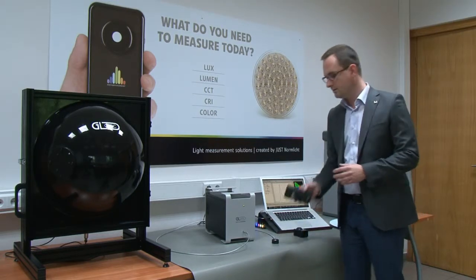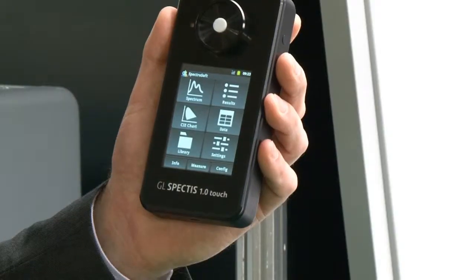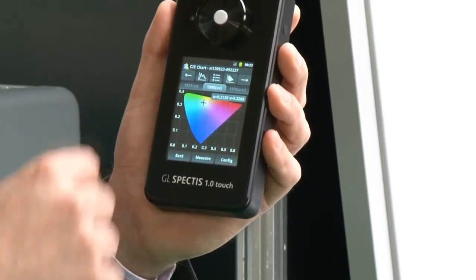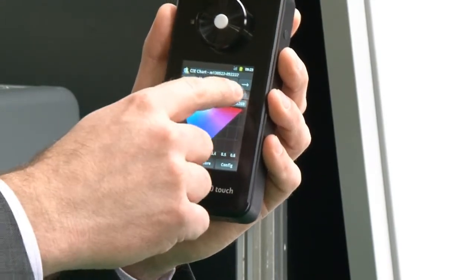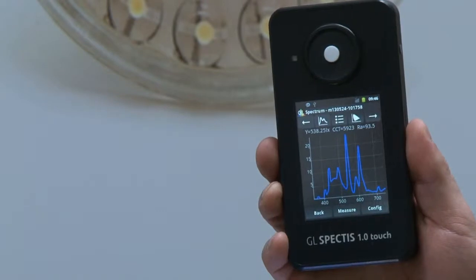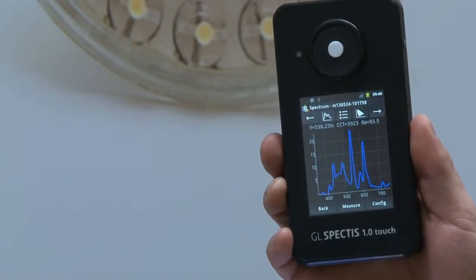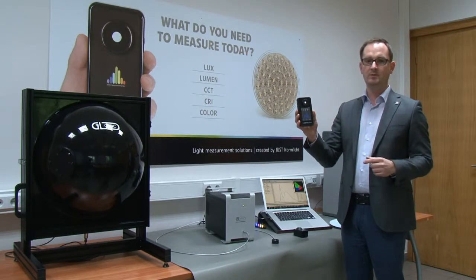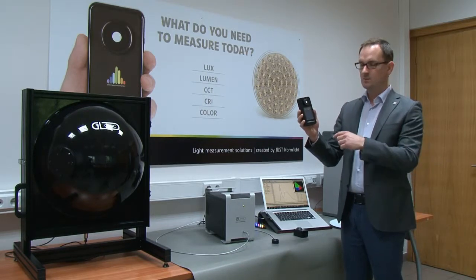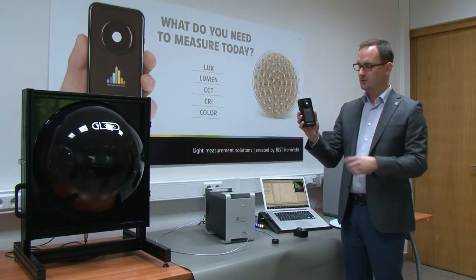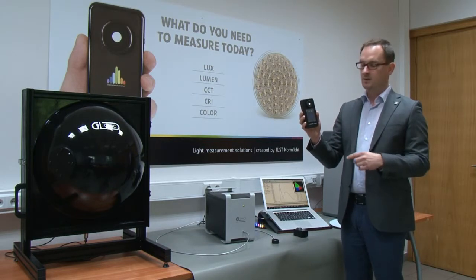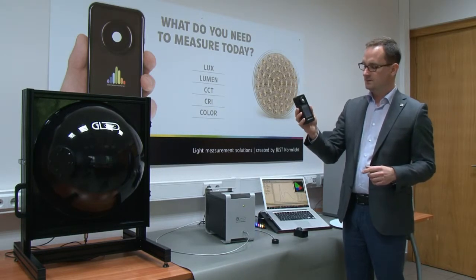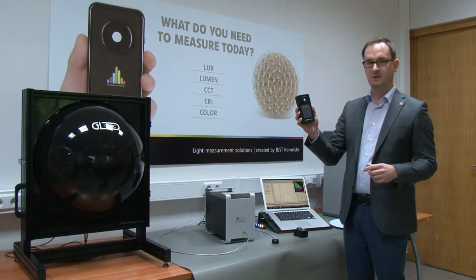Today I'm going to show you our handheld SPECTIS ONE TOUCH spectroradiometer, designed for light assessment, which can be equipped with a cosine corrector for illumination measurement. This way we can obtain the spectral power distribution and the value of illumination in lux, as well as other parameters calculated onboard. We are using an Android-based system and the calculations are made directly on the device when the measurement is taken.